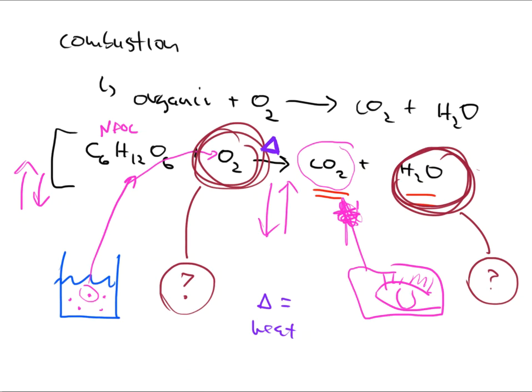In the last video we talked about the purpose of combustion — taking any type of organic molecule, carbon-based, and combining it with O2 and a little heat to produce two products: CO2 (carbon dioxide) and water. This reaction is the basis of the TOC instrument; the detector measures the amount of CO2 produced from the sample.